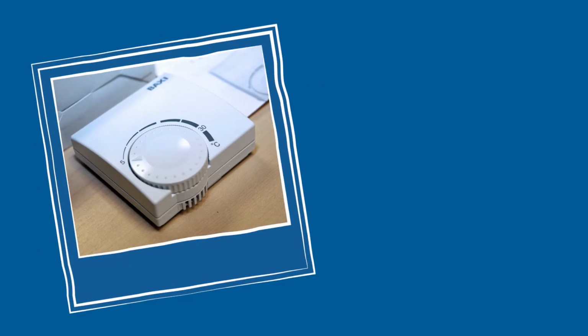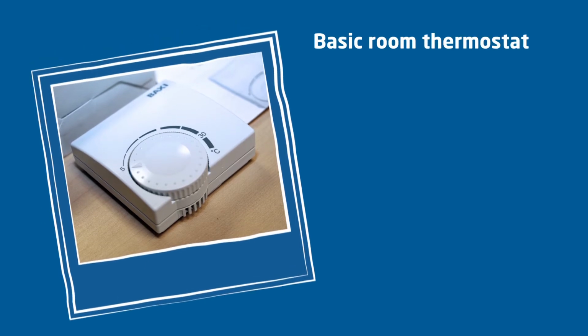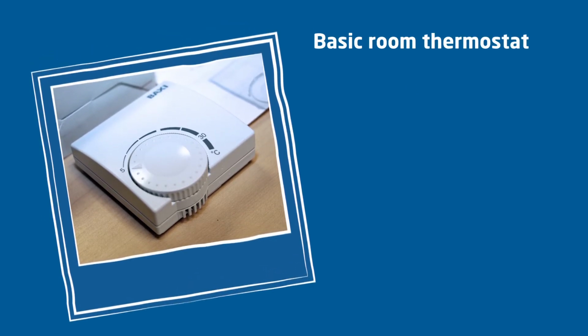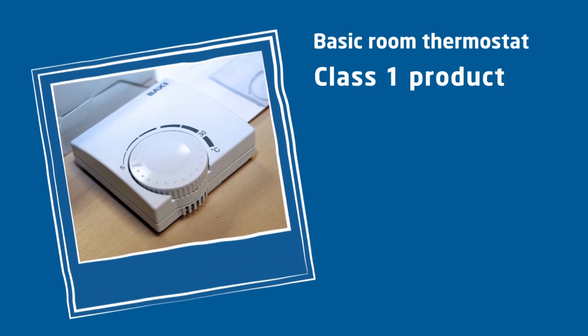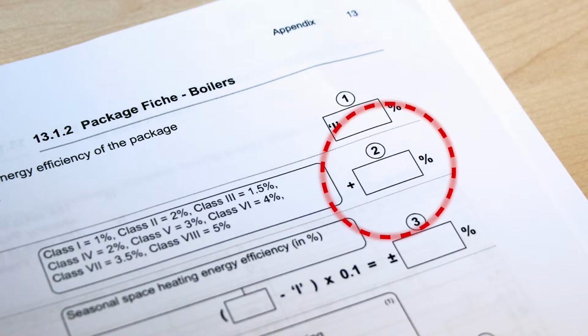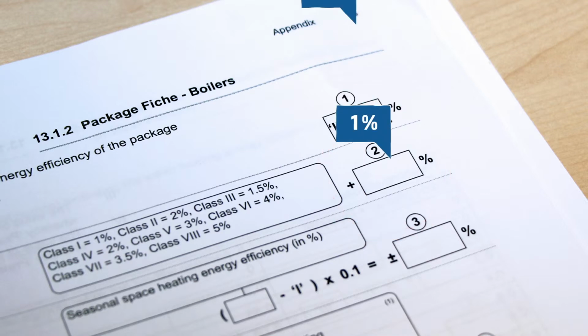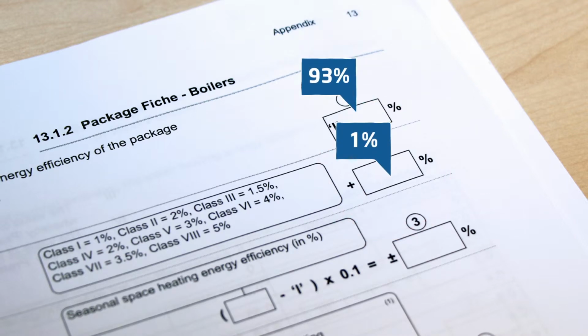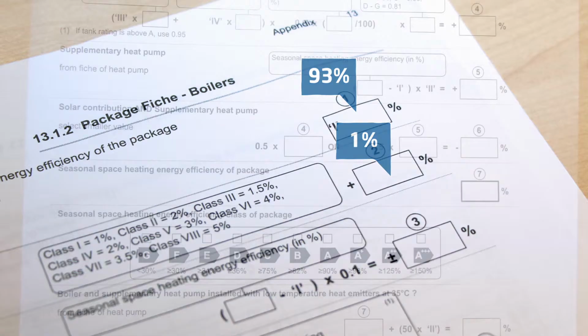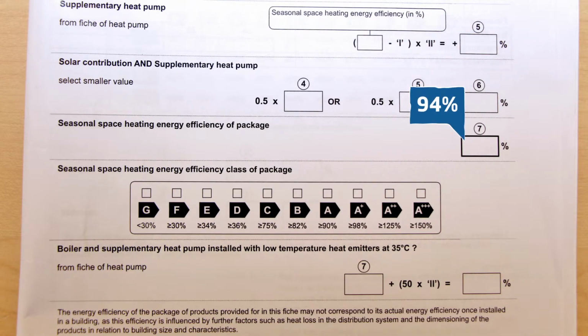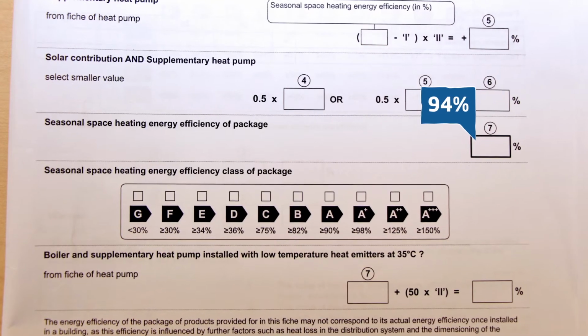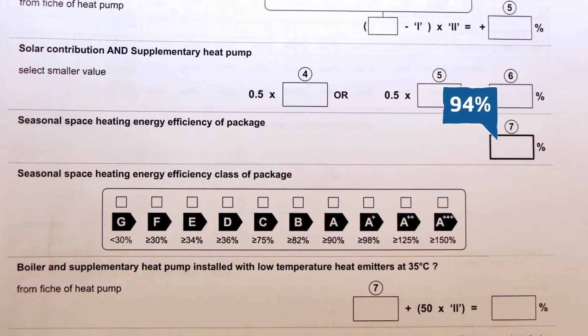In this example, we are fitting a basic room thermostat which has been rated as a Class 1 product, boosting performance of the package by 1%. In cell 2 of the package fiche, write 1%. Add the efficiency figures together from cell 1 and cell 2 and write the answer in cell 7. In this example, the efficiency of our package is 94%.